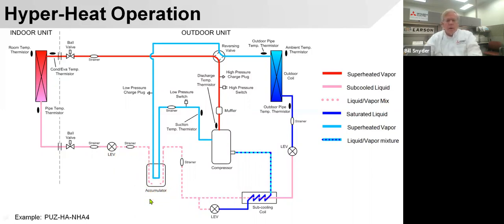hybrid accumulator, because you'll see this line dips into the accumulator, and the suction line, this blue line, is also going through there. We come out of the accumulator through another strainer, and we go straight through here through an LEV to the outdoor unit, which is now an evaporator. And we change from the subcooled liquid to a saturated liquid, go through another strainer, an outdoor entering coil pipe thermistor, and a leaving coil pipe thermistor, and an outdoor ambient temperature sensor, which is a thermistor, through the reversing valve, through the accumulator, through another strainer, a low pressure switch, a suction temperature thermistor, and into the compressor.